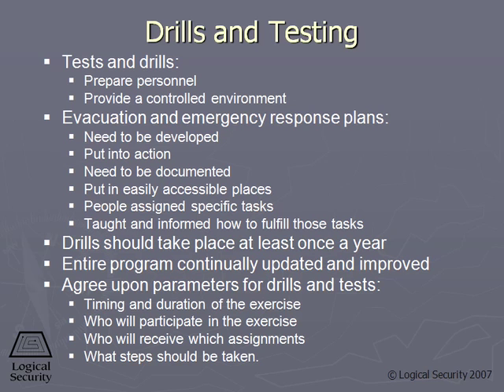Your users should be trained in emergency procedures. These procedures should be documented, readily available, and it should be a requirement of all employees that they read and understand these emergency procedures. Again, complete with training and drills. Regarding tests and drills, we need to have everyone in the organization well aware of what is expected of them in the emergency situation. They should know what they need to do. They should know how to evacuate and how to react. In other words, who to contact and what they should be doing in case of the emergency. These drills should be run at least once a year. We should always review and make sure that our plan is updated and is current because the facility changes. We add a new wing or we remove an area of the building. So all these should be reviewed and tested at least once a year.